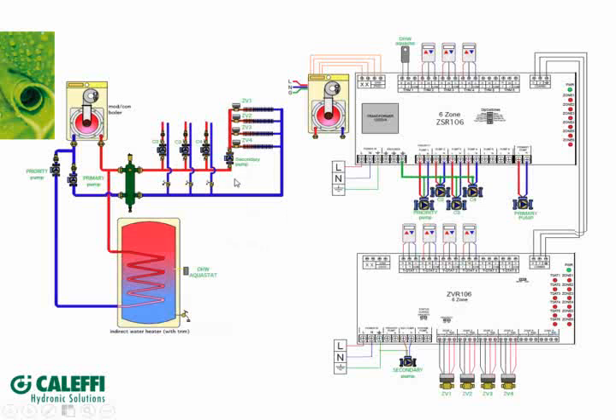Basically, we've got some circulators for zone circulators, primary pump, priority pump, and then like I mentioned before, maybe you're adding on another area to the home, and you just want to do another pump with zone valves. Well, we've got our pump board here communicating back to a valve board over here, and if one of the valves would call for heat, this thermostat calls for heat, powers up the zone valve. When the end switch closes, this secondary pump would fire. This board would communicate back to the master board that there's a demand.